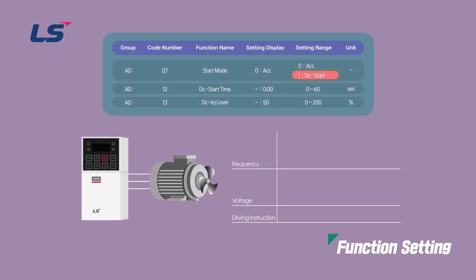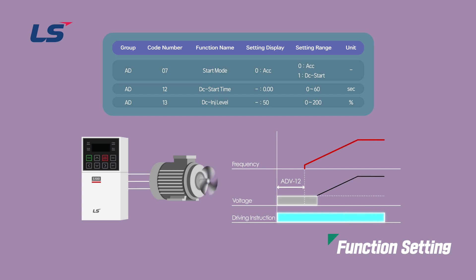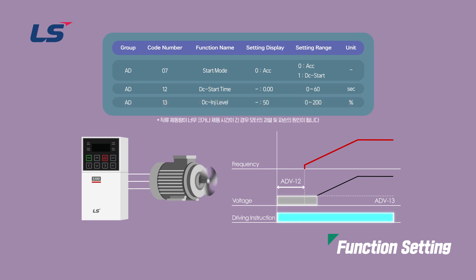The DC start method accelerates after applying direct current voltage to the motor for the set DC start time. If the motor is rotating before the voltage is output from the AC drive, DC braking will stop the motor rotation and then accelerate. It can also be used when a constant torque is required even after opening the machine brake under vertical loads using a machine brake on the motor shaft. The DC injection level can be set based on the motor rated current and should be set to a value within the AC drive rated current.